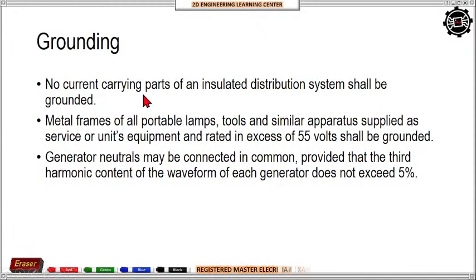So, grounding. No current carrying parts of an insulated system shall be grounded. So, lahat ng mga wirings natin sa barko, if that is live, or hot wires, hindi siya pwede i-grounded. No? Metal framings of portable lamps, tools, and similar apparatus supplied as service or units equipment rated in excess of 55 volts, this is line to ground, shall be grounded. Generator neutrals may be connected in common, common ang kanyang grounding, provided that the third harmonic content of the waveform of each generator does not exceed 5%. So when you say harmonic, yung fluctuation, yung pangatlong fluctuation ng kanyang voltage must not exceed 5% ng ating normal na voltage ng ating generator.